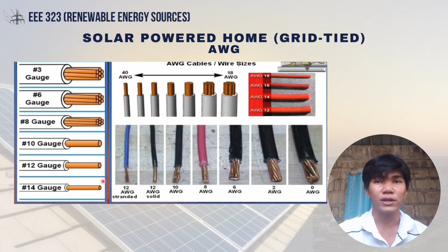Andito rin kung ito ay solid or stranded wire. Ito ang NEC Table 310.15(B)(16). Dito po yung allowable ampacities of insulated conductors rated up to and including 2000 volts, 60 degrees Celsius to 90 degrees Celsius, 140 degrees Fahrenheit through 194 degrees Fahrenheit. Not more than 3 current-carrying conductors in raceway, cables, or earth directly buried, based on the ambient temperature of 30 degrees Celsius or 86 degrees Fahrenheit.